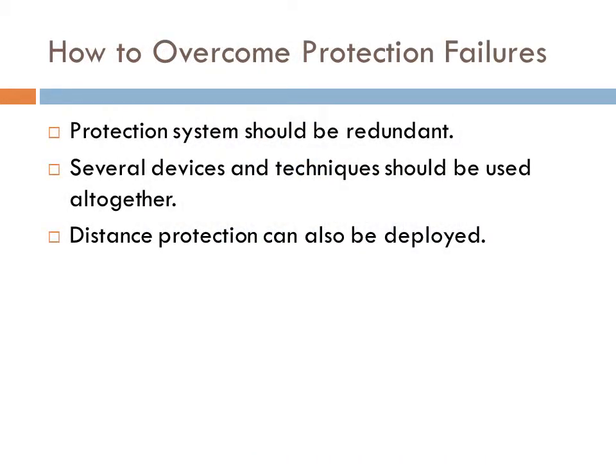Now the question arises how to overcome protection failure. Protection system should be redundant, i.e. uninterruptible power supply. If a fault occurs, the system is designed in such a way that it does not interrupt the whole system but isolates the faulty part. For this purpose, several devices and techniques should be used together. Distance protection can also be deployed.